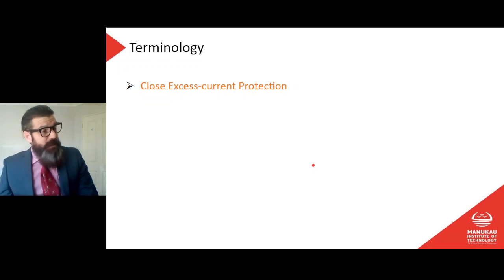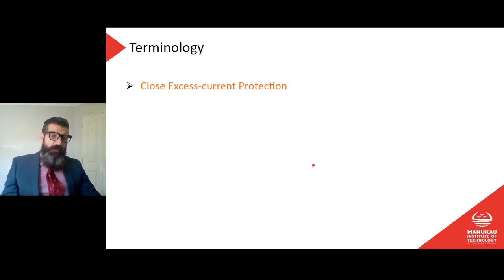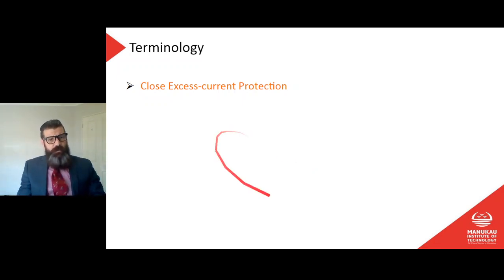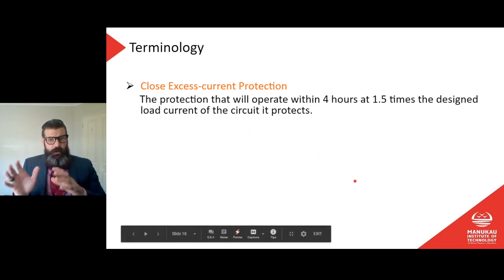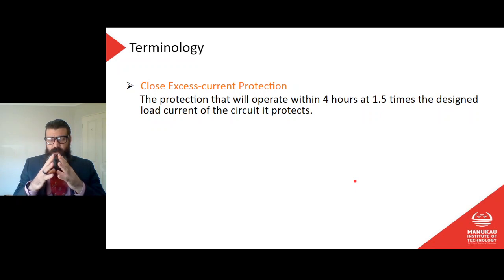Next one's close excess current protection. This is worth remembering, the difference between close and coarse excess current protection. We've talked about this before, right? This is a circuit breaker or fuse that will operate within 4 hours at 1.5 times the designed load current of the circuit it protects. So if I have a 20 amp circuit breaker and I put 30 amps through it, as long as it trips within 4 hours, that is deemed to be close excess current protection.